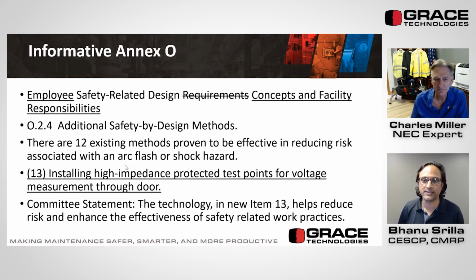Additionally, you need to understand it's not just any extension of test leads. On a previous public input I submitted, the committee also identified that it's not just any test points that can be put outside the cabinet. Those must also be listed and labeled to UL 61010 standards. So this is another method of verifying absence of voltage from outside the door.